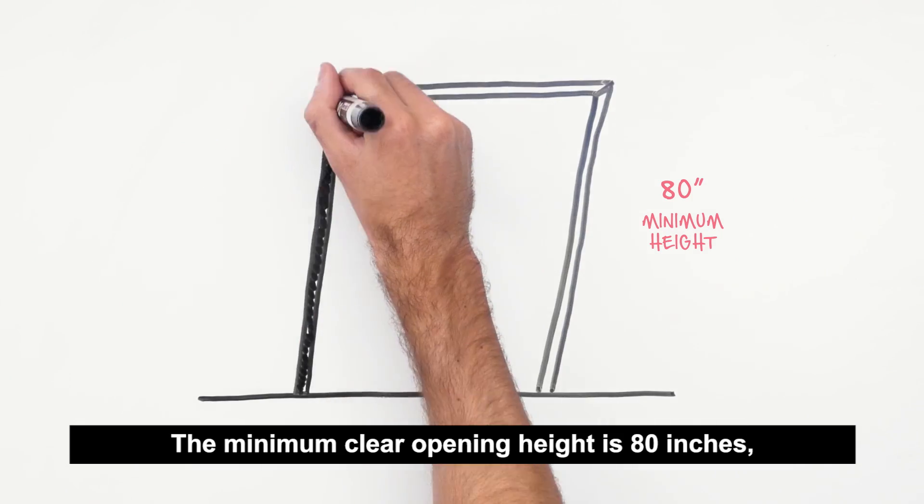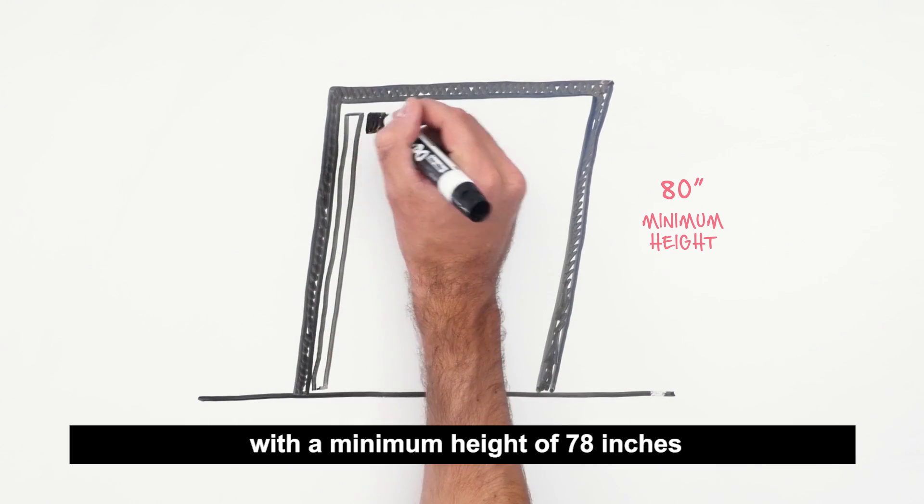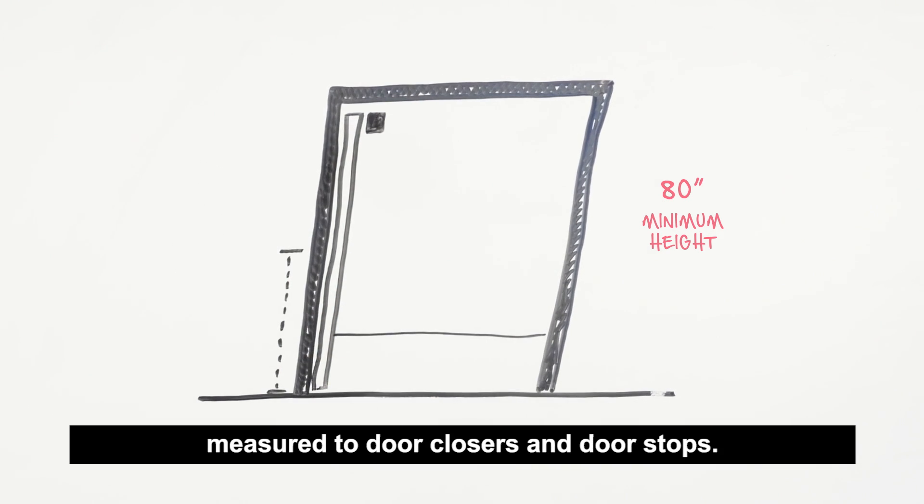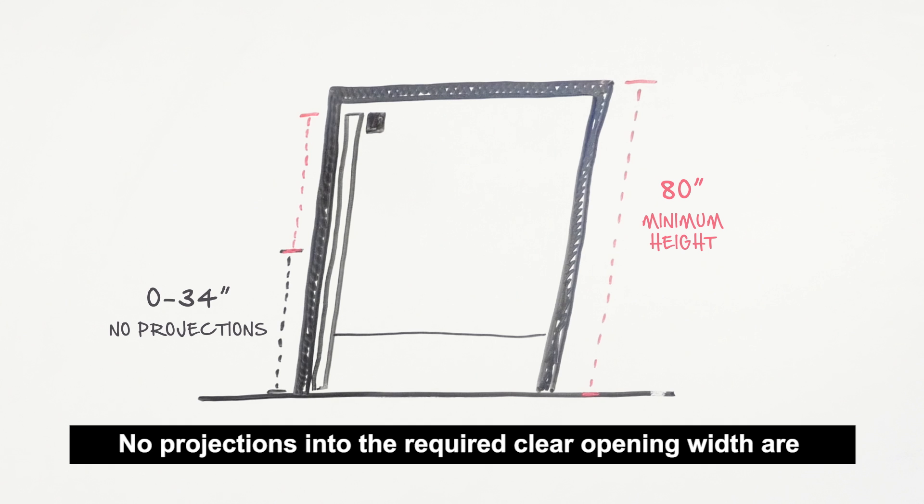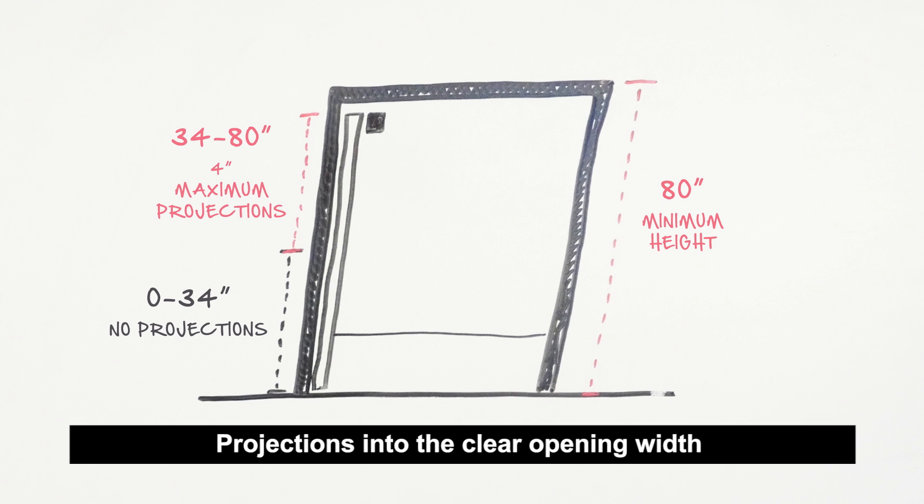The minimum clear opening height is 80 inches, with a minimum height of 78 inches measured to door closers and door stops. No projections into the required clear opening width are allowed below 34 inches above the finished floor or ground. Projections into the clear opening width above 34 inches are limited to 4 inches.